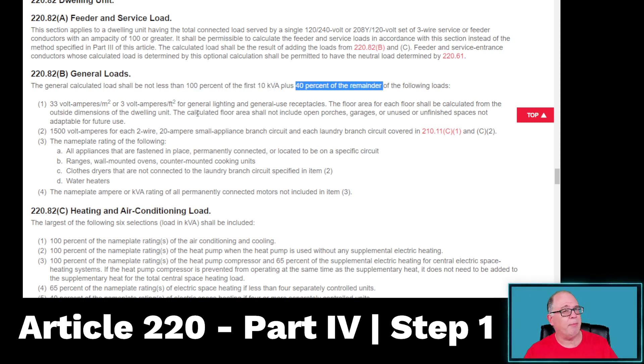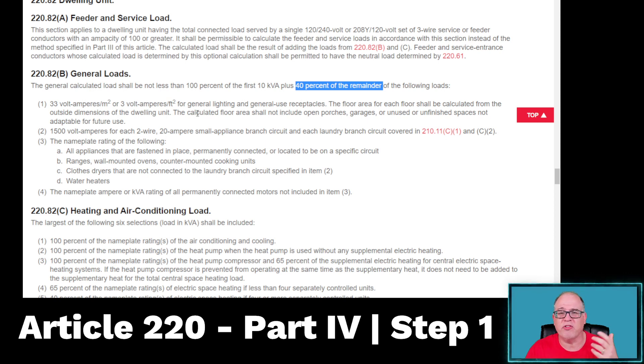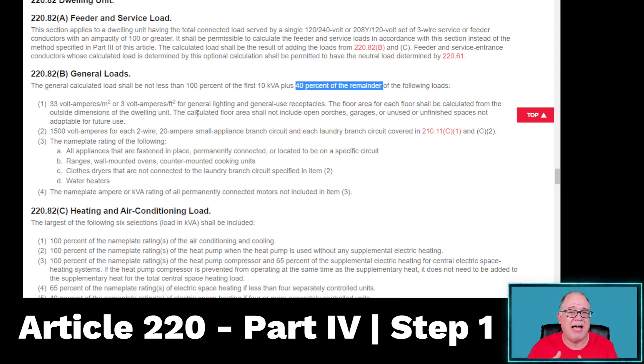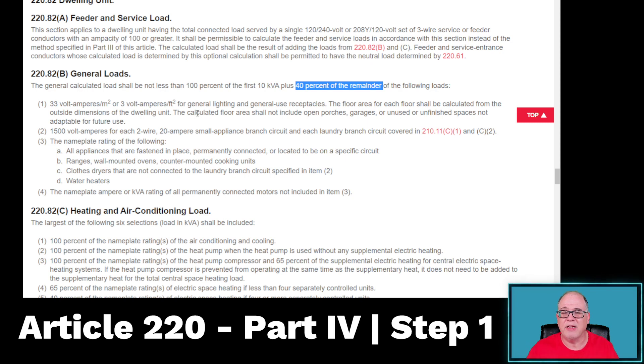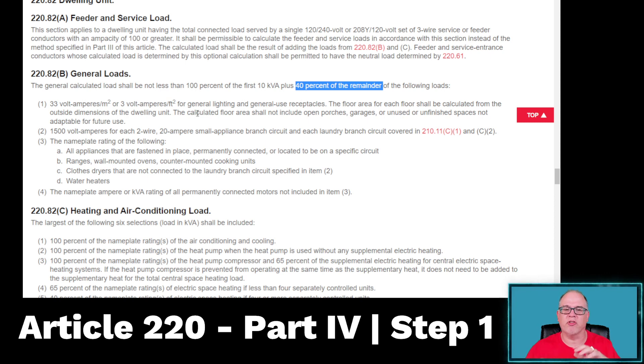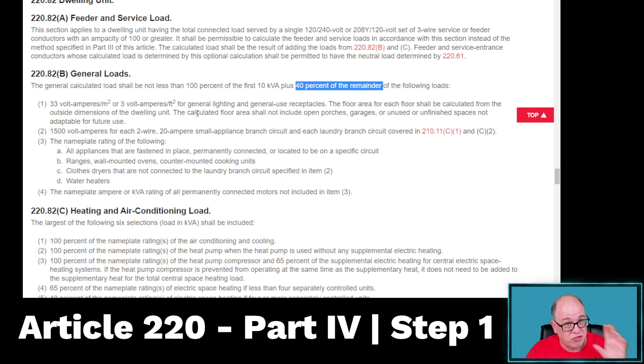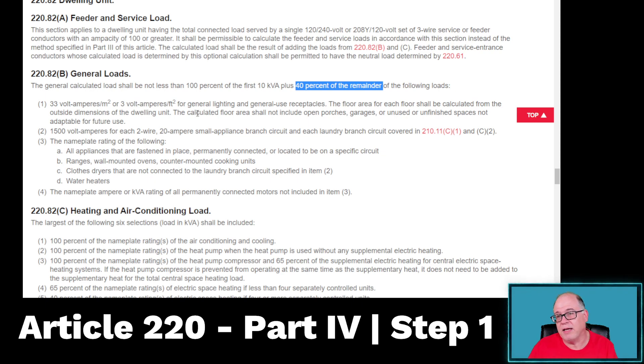That's a pretty hefty demand factor. Remember in the standard method, we got 75% for appliances if we had four or more, and we had to apply demand factors for general lighting — first 3,000 at 100%, the next 117,000 at 35%, and the value over 120,000 at 25%. We don't have to do any of that here. Also, when it comes to ranges, clothes dryers, water heaters, and other fixed-in-place appliances, we just take the nameplate. Then when you get to 220.82C — heating and air conditioning — we take the larger. We take the values from 220.82B, add the values from 220.82C, add them together, and that's how we do it for an individual dwelling unit using the optional method.